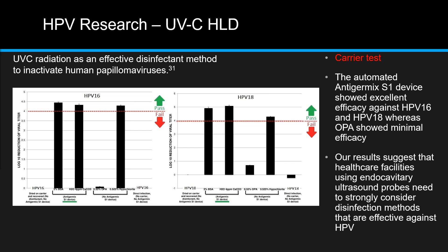can cause that log-4 reduction. But if you look in the middle where we used OPA, this has been a classical high-level disinfectant. It didn't even reach a 1 log reduction in this study. So the automated Antigermix S1 device showed excellent efficacy against HPV-16 and HPV-18, whereas OPA showed minimal efficacy. And our results suggest that healthcare facilities using endocavitary ultrasound probes need to strongly consider disinfection methods that are effective against HPV. And I will point out that this study was done using discs that were made out of the same material that probe handles are made out of. Next slide, please.